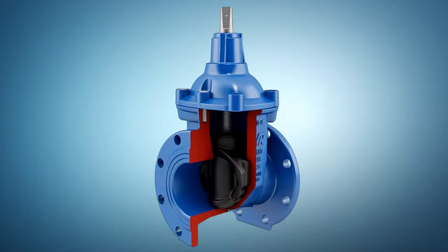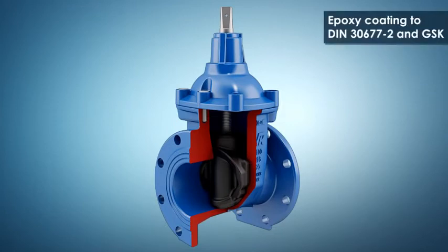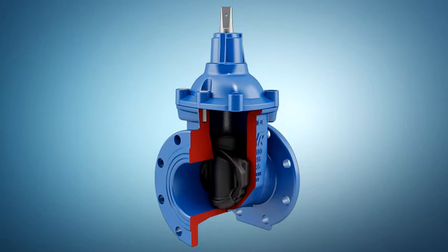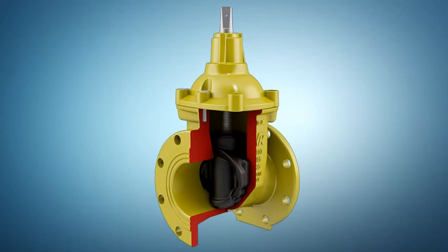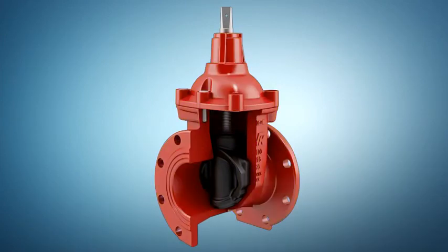AVK gate valves are as standard with internal and external epoxy coating to DIN 30677-2 and the strict GSK requirements. The valves are blue for water and wastewater treatment, yellow for gas, and red for fire protection.